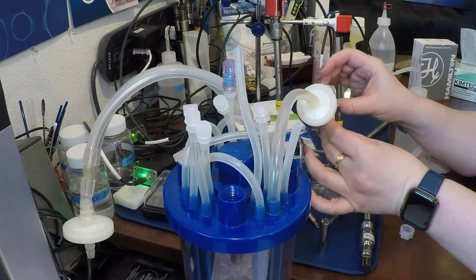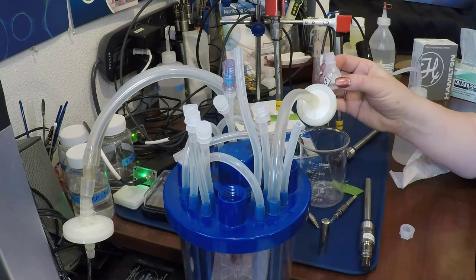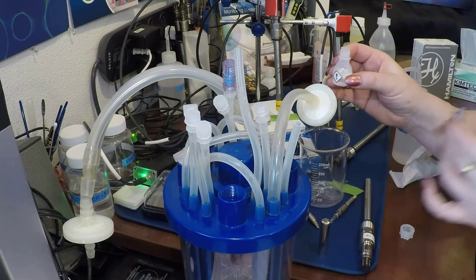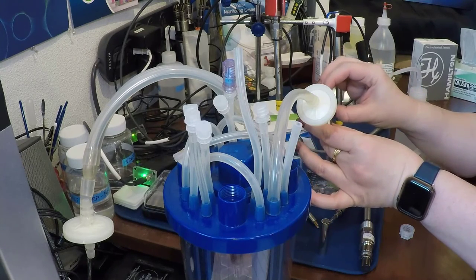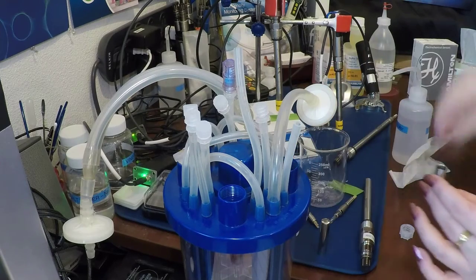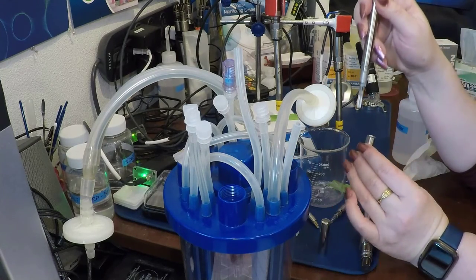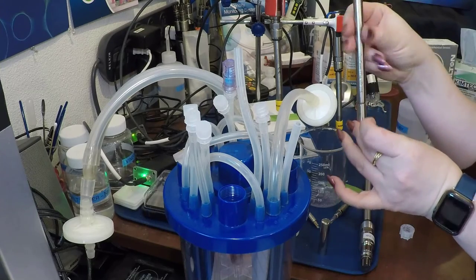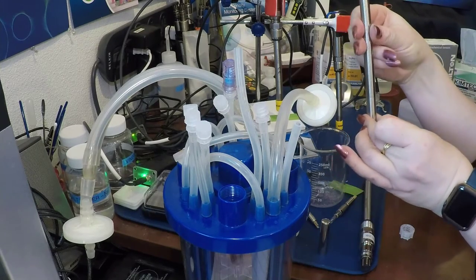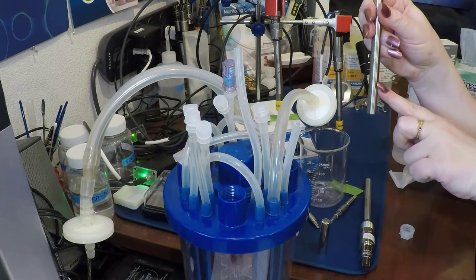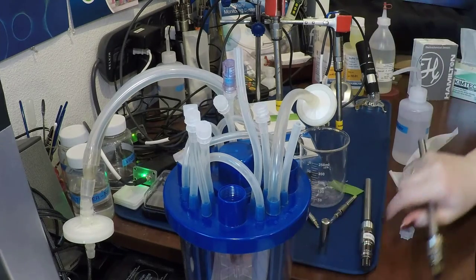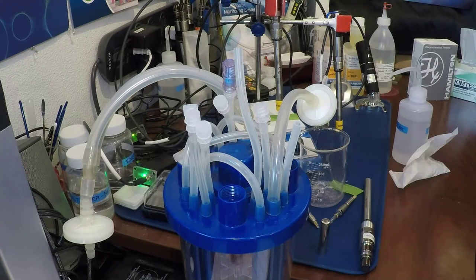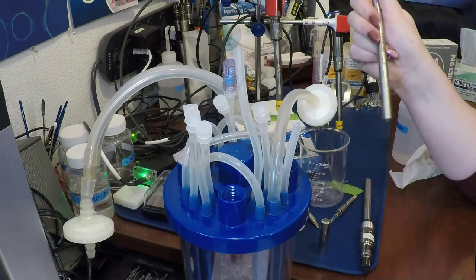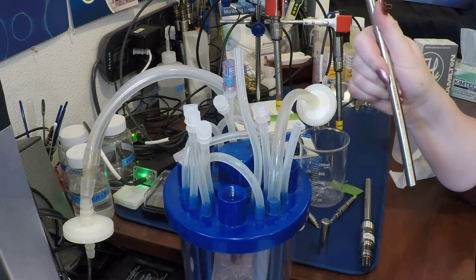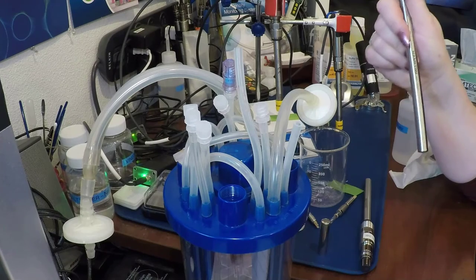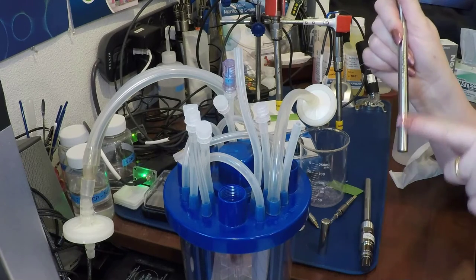And you're going to carefully measure in 1 to 1.2 liters. I don't have my measuring device right now, but you'll measure that in here. Okay, I'm just going to put a little bit in. You want to make sure you do not put more than 1 to 1.5 liters. So when you put this in, it will leave a small air gap in here. And again, carefully measure, don't do what I just did. 1 to 1.5 liters. Now that's specific to Hamilton probes. If you have a probe from a manufacturer that's not Hamilton, read the manual they give and ask them, because everybody has a slightly different capacity.